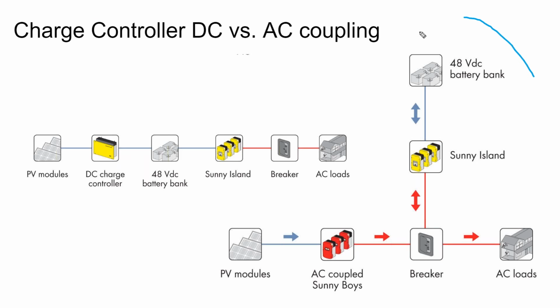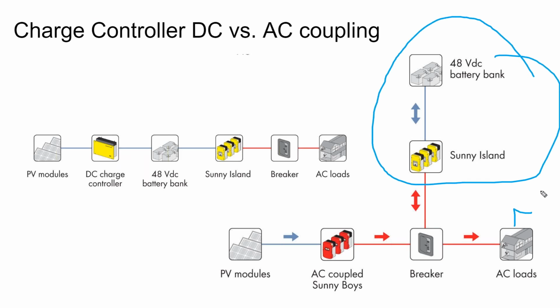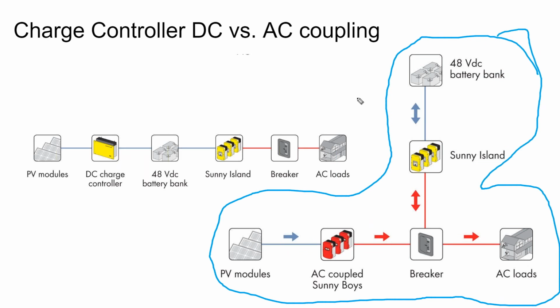AC coupling is also very popular when you have that grid connection, because on an AC coupled system, the battery may just hang out and not do anything until there's a power outage. So you don't incur that 1, 2, 3 step process - you just direct drive your load with solar, and any surplus goes out onto the grid. That's a one-step process. So AC coupling has real advantages even when you have batteries if you're grid tied, and that means the whole grid-tied and batteryless market kind of rewards the AC coupled architecture.